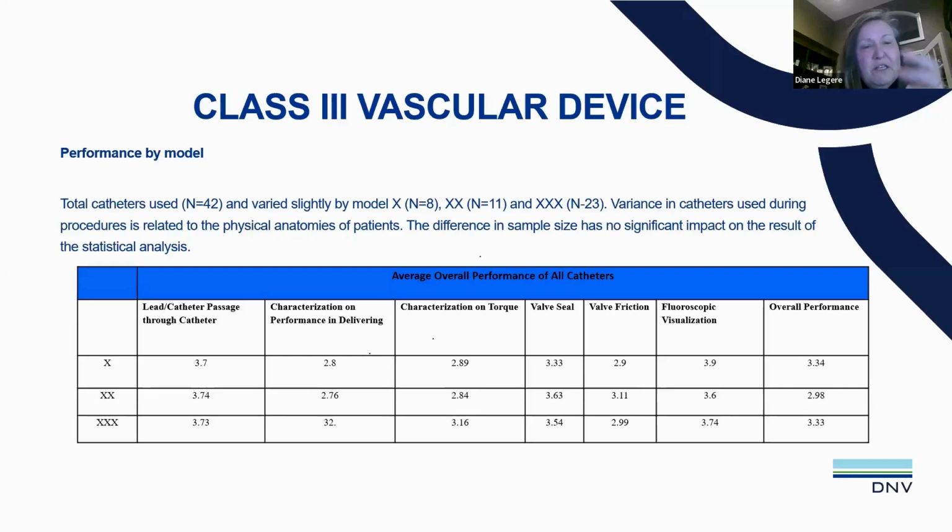My previous question was, I need to see that in your clinical assessment and your risk management, you've clearly identified any gaps in age, in variance, in models, in any of it, because the expectation is that you will have clinical data to support the whole spectrum. We know it's never perfect. So you're going to provide a justification of why you believe it is still going to perform as intended and be safe, and you're going to target that and get that data in your PMCF. That is the expectation.